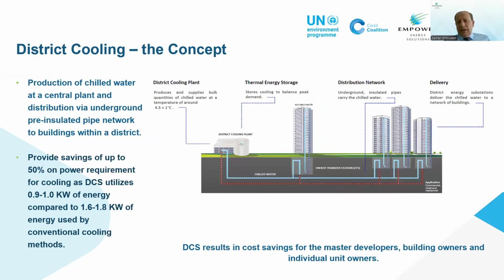The concept mainly has 3 elements: a plant room where we produce chilled water at 4.5 degrees, an underground network through pre-insulated pipe, and delivery of the chilled water to each building through an energy transfer station. This model ensures the building's system is segregated from the district cooling provider's system, giving better control over supply and return temperature.